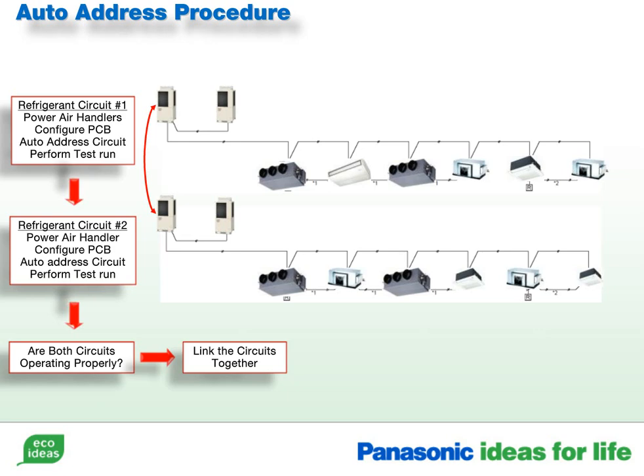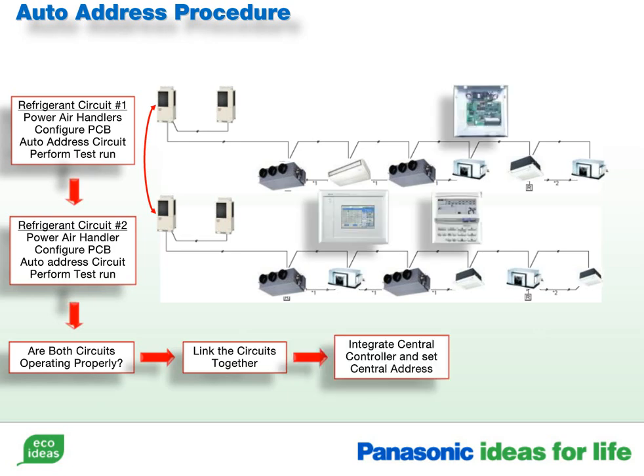Now the refrigerant circuits can be linked together via the U1 and U2 connections. We recommend making this connection at the outdoor unit. At this time, introduce the intelligent controller or the system controller to the SNET. You will also need to initiate the central control address setting in the device you have installed.